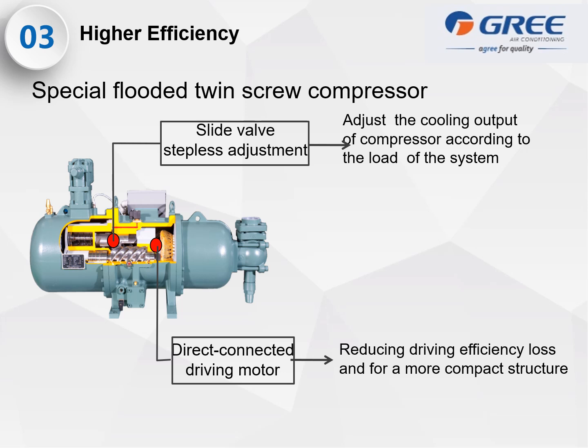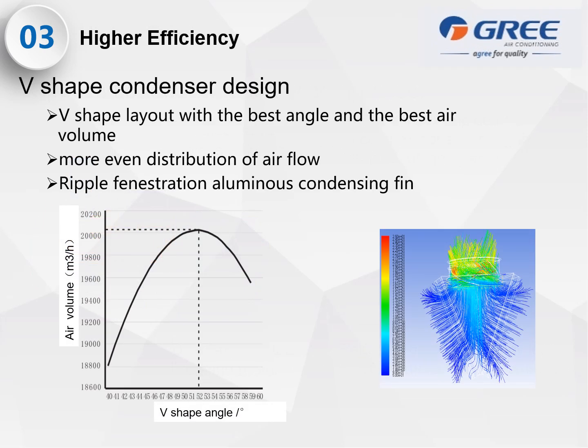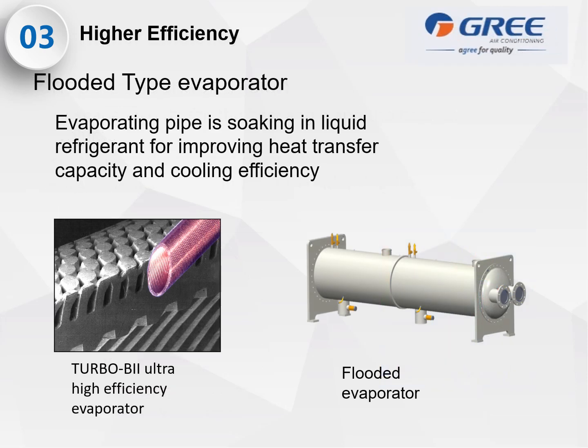For the special flooded twin screw compressor, it has a slide valve stepless adjustment, meaning it adjusts the cooling output of the compressor according to the load of the system, reducing driving efficiency loss. For a more compact structure, it has a direct connected driving motor. The V-shaped condenser design has the best angle and the best air volume, with more even distribution of airflow, ripple fenestration, and aluminum condensing fin. For the flooded type evaporator, the pipe is soaked in liquid refrigerant for improved heat transfer capacity and cooling efficiency.